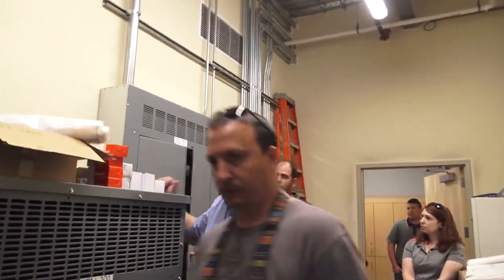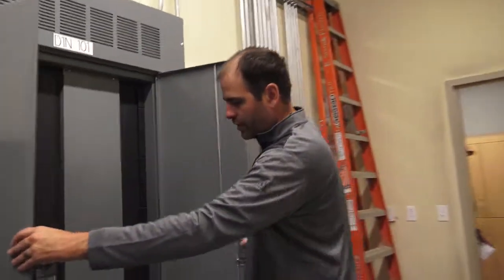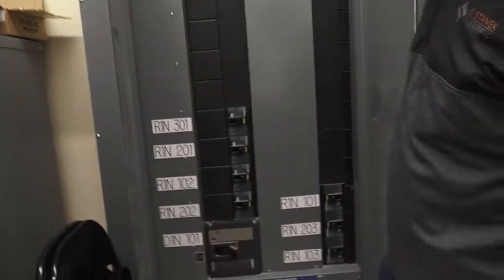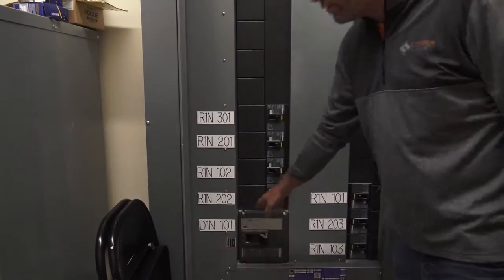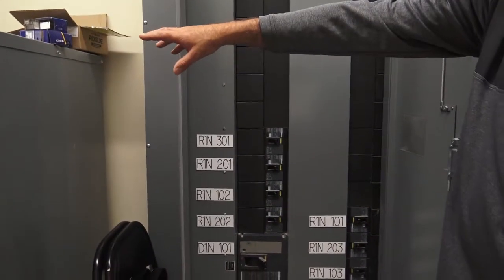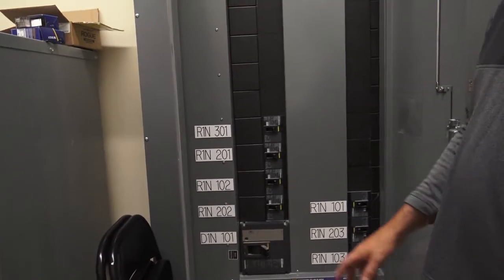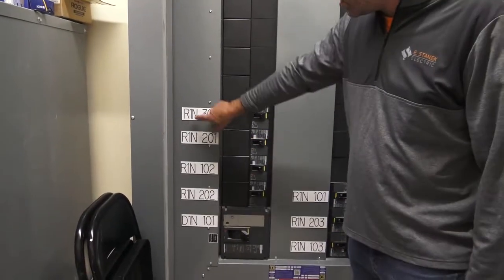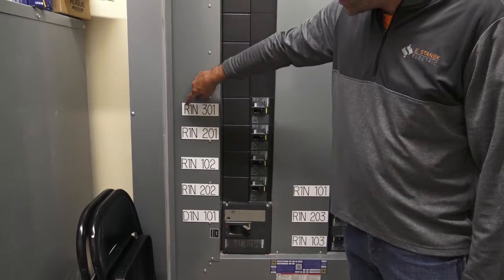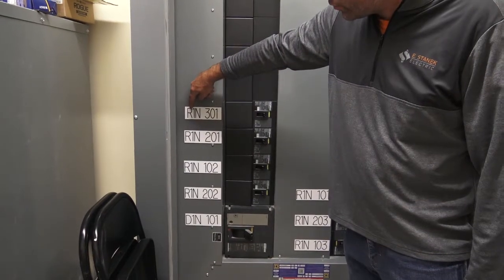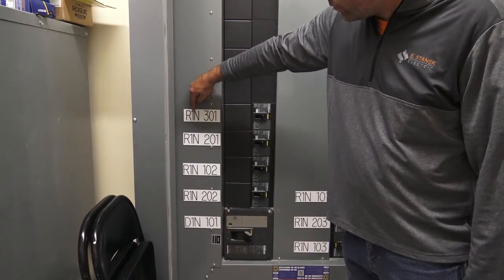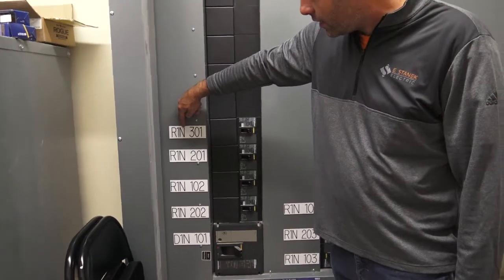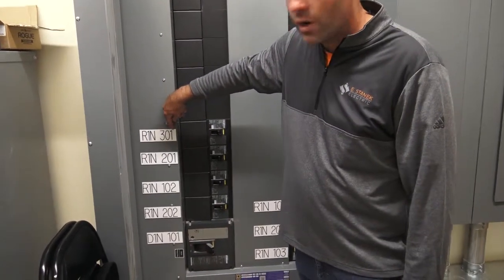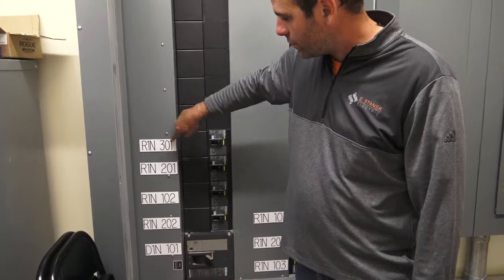This panel over here is the low voltage distribution, which is 120/208. We've got a main breaker fed directly from the transformer. All these panels are labeled R1N — R for receptacle panel, 1 for the voltage 120/208, N for normal, and 301 would be our third floor panel, the first panel.